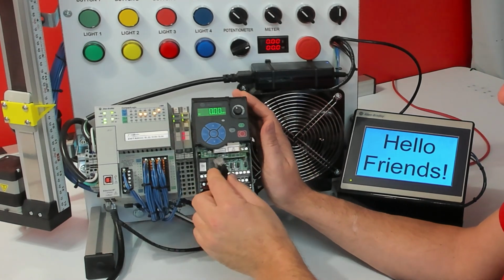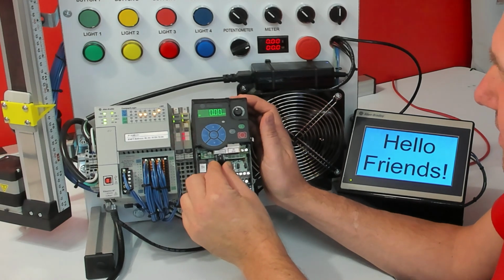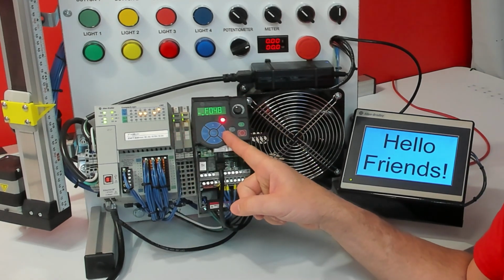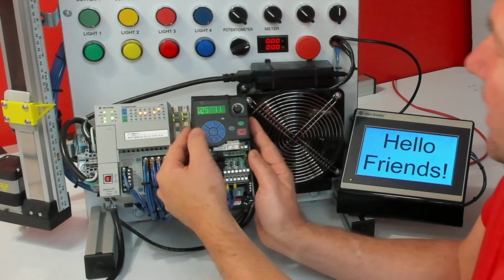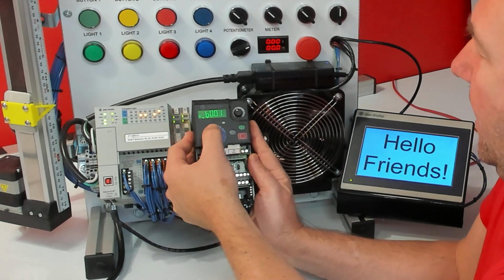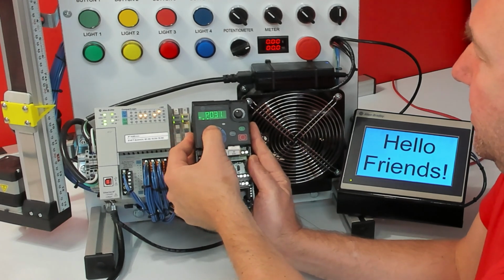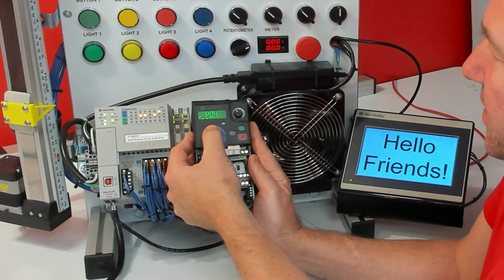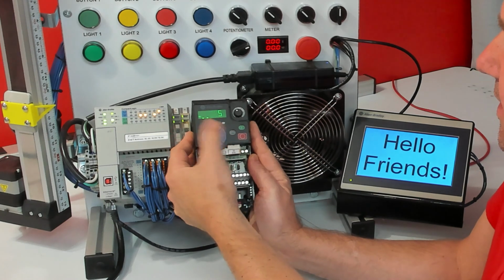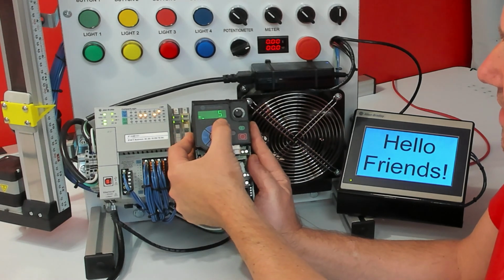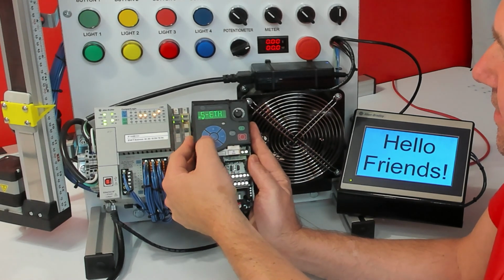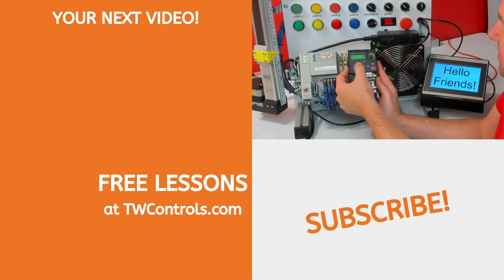Now I'm going to plug my Ethernet cable back in. And momentarily, we get a fault F48, and then it's going to reboot. And now I'm going to go back into my P parameters and look at 46 again. And now it's at 5, which is Ethernet IP. And if we go up to P47, it's back at 15, which is Ethernet IP.